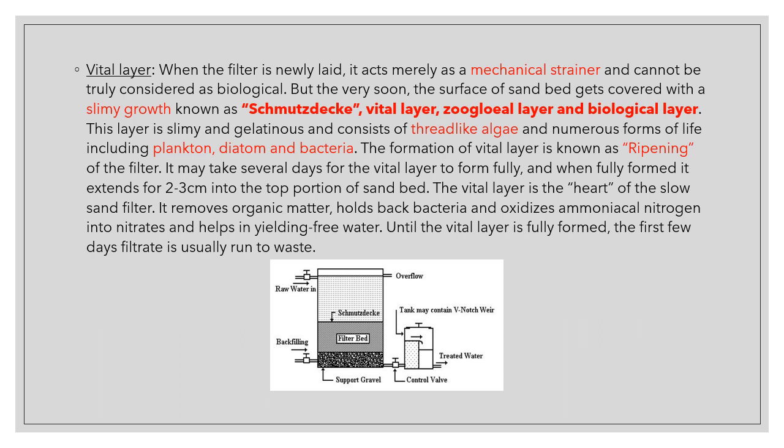which helps in yielding free water. And until the vital layer is fully formed, the first few days of filtrate is usually run to waste. This means that when we set up the new filter for the first time, we're not going to use the water that is filtered out for the first, say, 3-4 days. The reason being that the vital layer hasn't completely formed yet. So it just comes to show how vital this vital layer is.